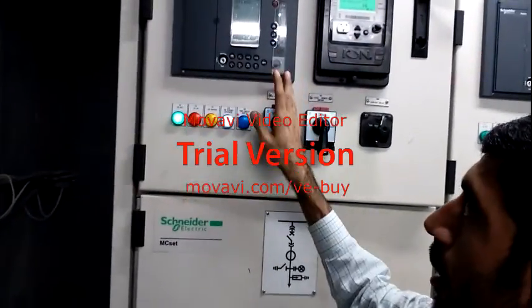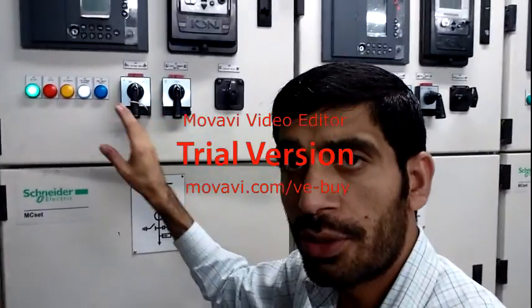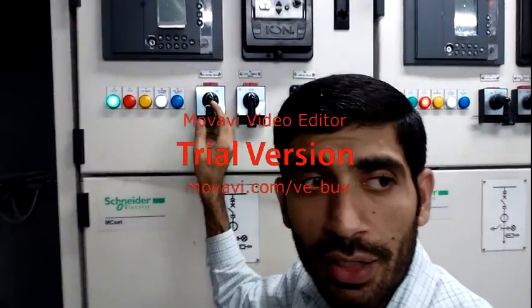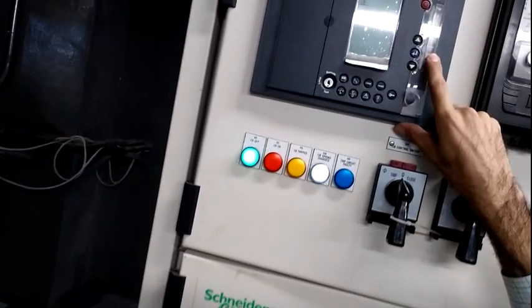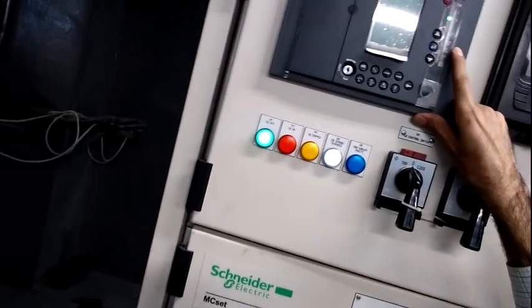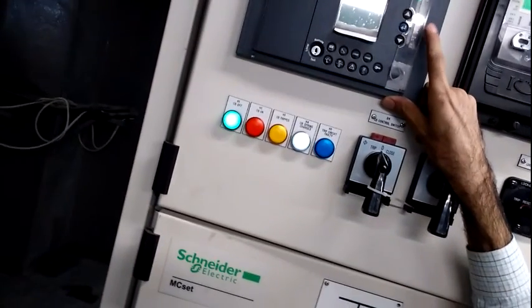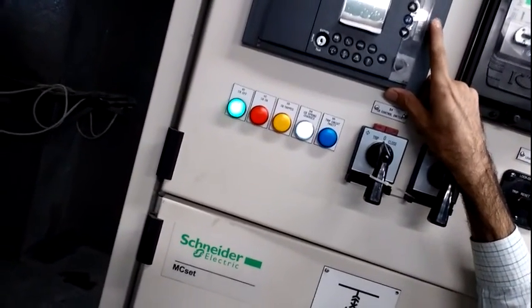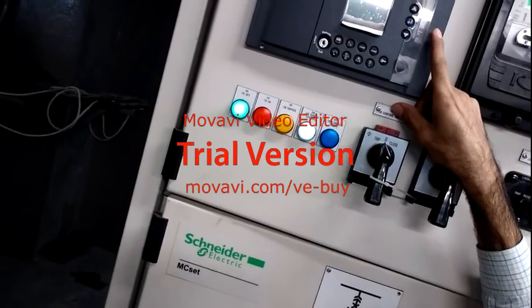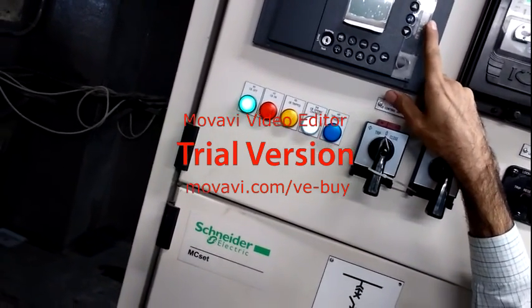This is the protection relay. I told you before about the protection relay. This protection relay is used for different protections: over current protection, under voltage, over voltage, earth fault, and short circuit. We use it for all of these. You can see here, this is over current. We use it for over current and earth fault, step 1, step 2, over current step 1 and step 2. These 4 indications are glowing here on this relay.